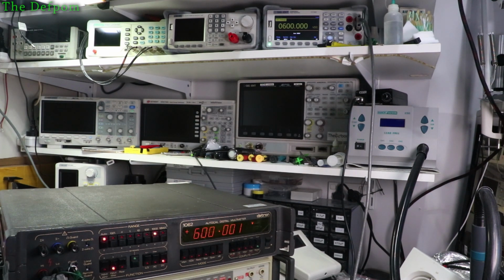Let's keep on going up. You can see they agree pretty well. Certainly on these high ranges, the noise becomes negligible, so those positions get much more consistent. The linearity is looking really good. At 1000 volts, they still agree, so I'm happy with that. At least the linearity side of it is good, on the higher scales certainly.